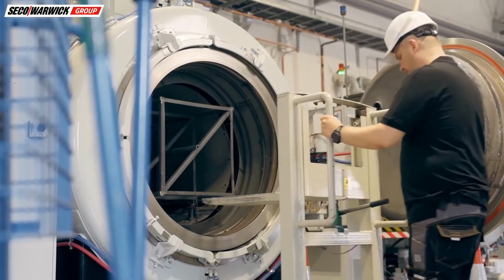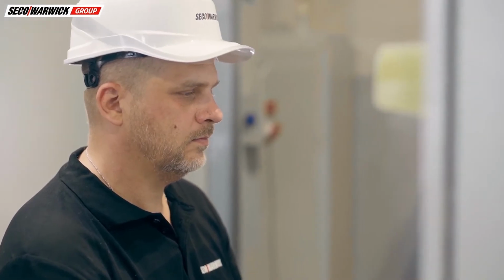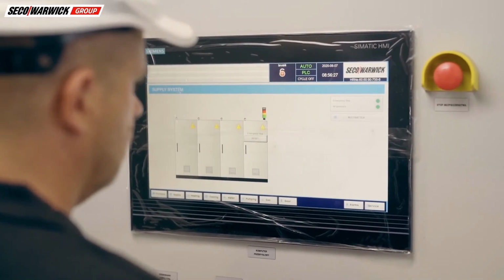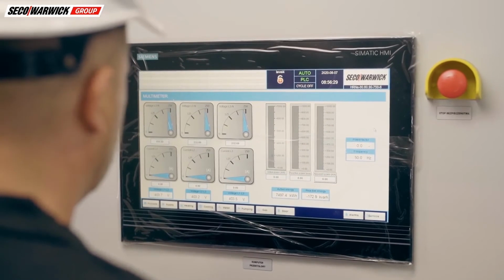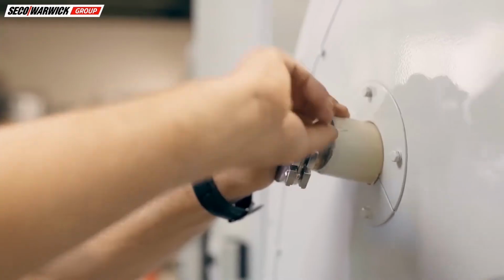As a standard practice, the service engineer also checks all other furnace systems for proper operation. After this repair, all heating zones are working properly and are equally activated. The furnace is also working properly, and we can start the requested temperature uniformity survey.